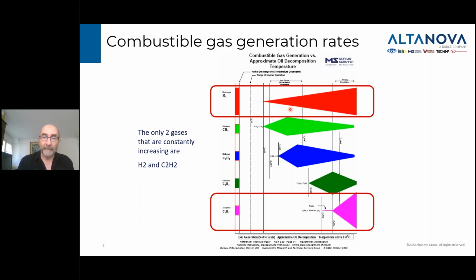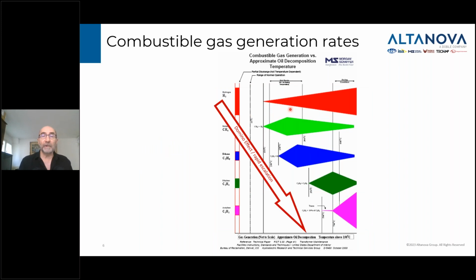But mostly, when you look at this, there are only two gases that are constantly increasing, hydrogen and acetylene. And what you have is what you call a domino effect. As the fault evolves and its temperature evolves, one gas's rate of generation increases and decreases when another gas's rate of generation increases, until you reach the point where you're mostly generating acetylene. So when you have a very accurate DGA, just by measuring the gases it gives you a lot of information: where you stand on that curve, that graph, telling you exactly, potentially, where you are from a temperature point of view.